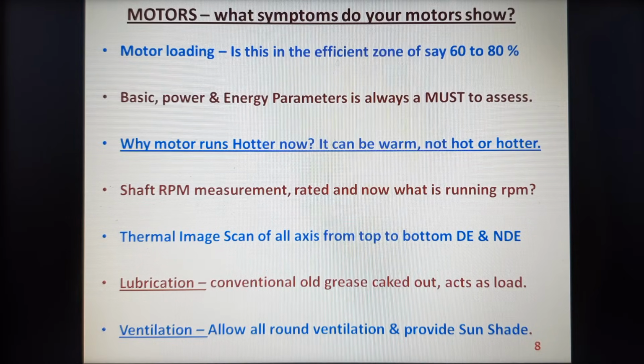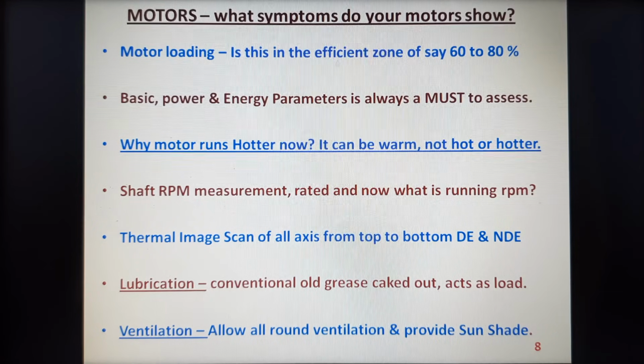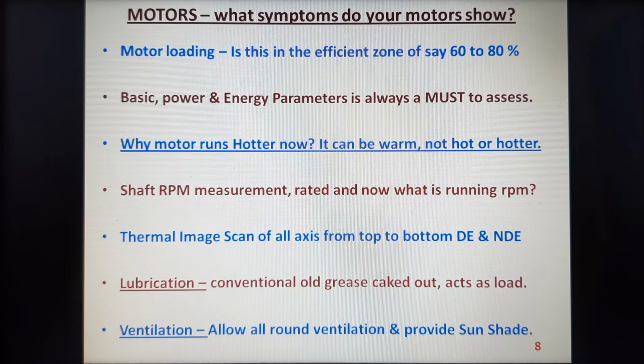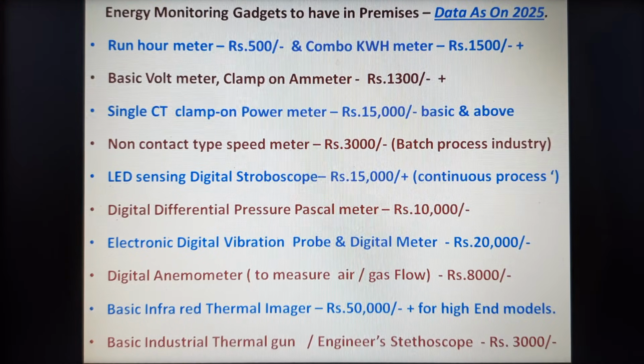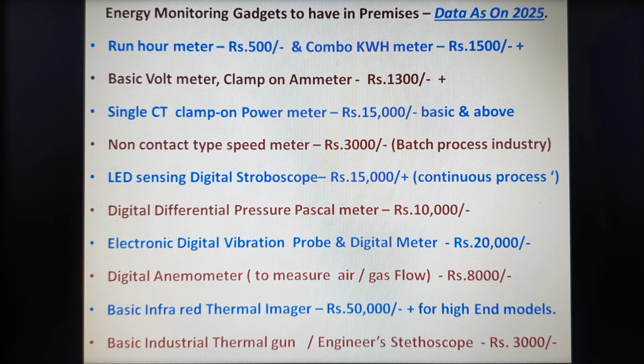Coming to the ventilation of the given motor, all-around ventilation should be there for the motor so that the motor fins get good cooling. Being a TEFC motor, totally enclosed fan cooled motor, the ventilation should be there on the motor fins all around. Definitely this will maintain the motor healthy as such. The energy monitoring gadgets can be there in our premises, or it can be outsourced. These are all the areas which we can concentrate on.